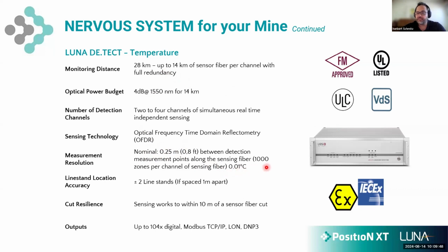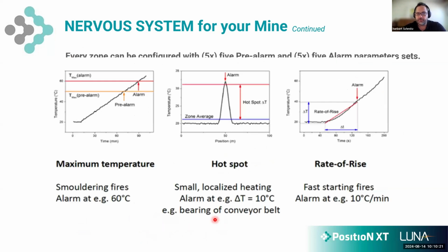Now, for every single channel on this box, and let's say we have 4 channels, we can configure 1,000 zones. Each of these zones, we can configure 5 unique pre-alarm and 5 unique alarm criteria. And I'll go into a bit more depth with that just now. Fully integratable, up to 104 digital outputs, Modbus TCP IP, LON, DNP3 to interface with the current ventilation, SCADA, control systems within the mine.